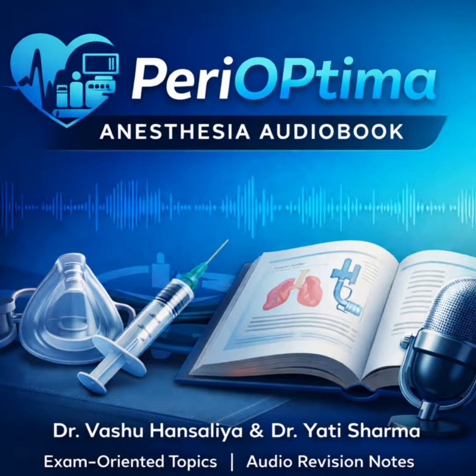And its core purpose is really twofold. First, it's about the precise delivery of the anesthetic and oxygen mixture, the fresh gas flow, or FGF, to the patient. Right. It has to maintain the required partial pressure of the volatile agent. Second, and this is just as important, it has to efficiently manage the patient's expired gases, ensuring the safe, reliable elimination of carbon dioxide, while maybe allowing for some partial rebreathing. That clarity is absolutely essential.